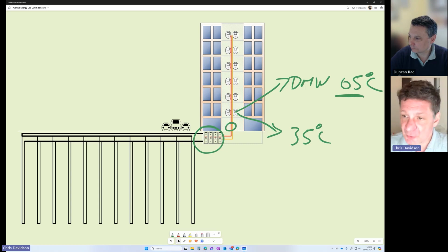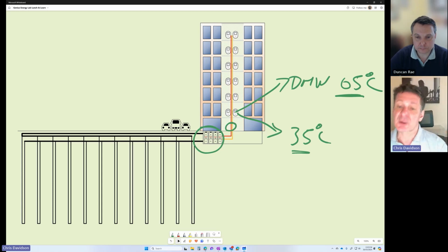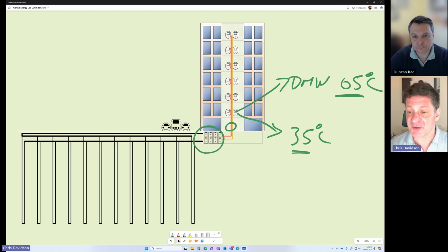We're therefore running our heat pumps at a higher temperature. The thing about heat pumps is that the higher temperature we deliver, the less efficient it is, consuming more electrical energy. The best way to think about it: climbing a small hill is less work than climbing a high mountain. So a heat pump climbing to 35 degrees does less work than climbing to 65 degrees. We're compromising the space heating efficiency that could be achieved at that lower level, as a result of delivering heating at the higher temperature needed, because we've only got one riser to work with.